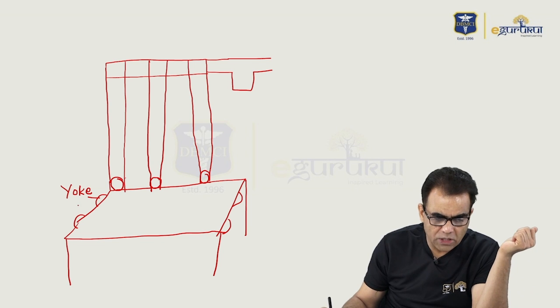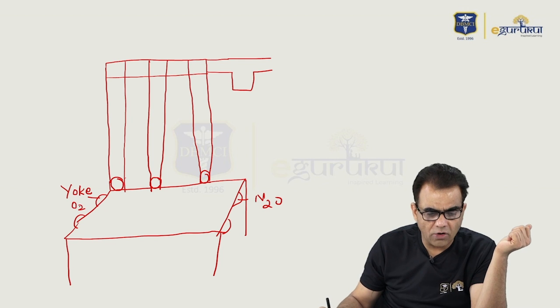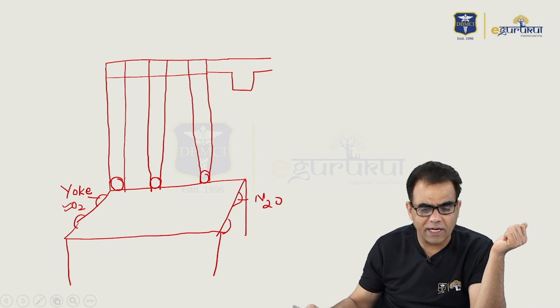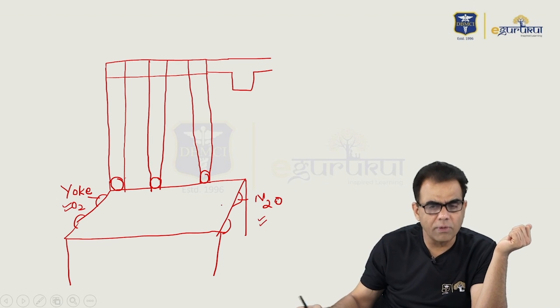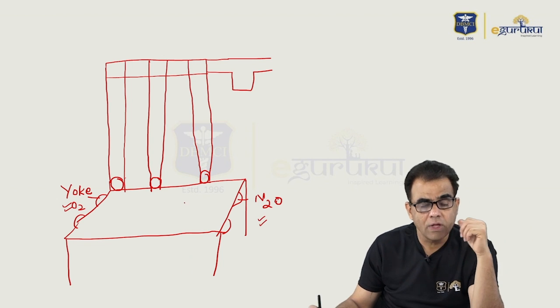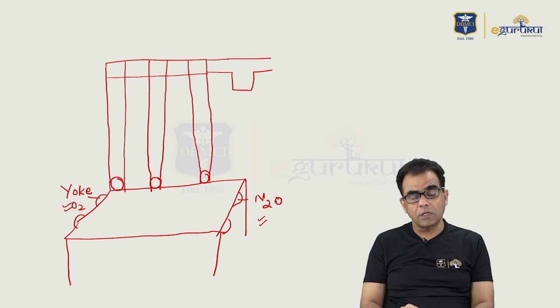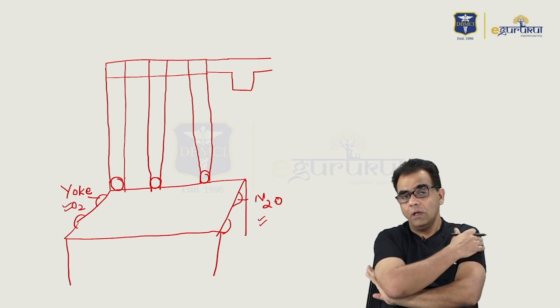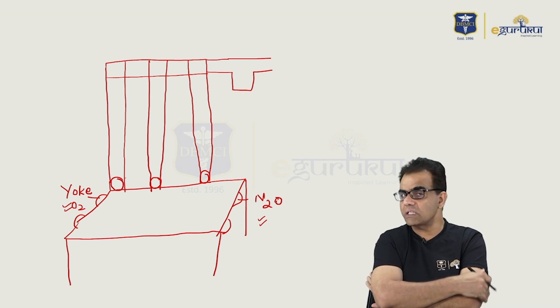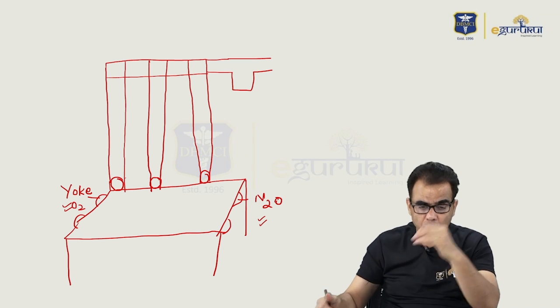This is the yoke for oxygen and this is the yoke for nitrous oxide. So obviously, the oxygen cylinder or central supply will be attached here, and the nitrous oxide central supply or cylinder will be attached here. But the pressure in cylinders or even central supply is very high — 2000 PSI can blast everything, so obviously pressure has to be reduced.